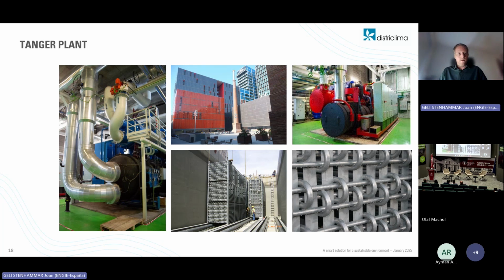It's important to understand that when storing cooling, you need more space than with heating, just because of the delta T, the delta temperature that you have in climatization for refrigeration in comparison with heating. Before, we saw that the storage accumulation we have in Forum is 5,000 cubic meters, and that gives us up to 40 megawatt hours. But here, since we are taking the benefit of the change of phase into ice with half of the volume, in the ice storage tank of 2,500 cubic meters we can store 120 megawatt hours. So there is a ratio of 6 times less space when using change of phase with ice.